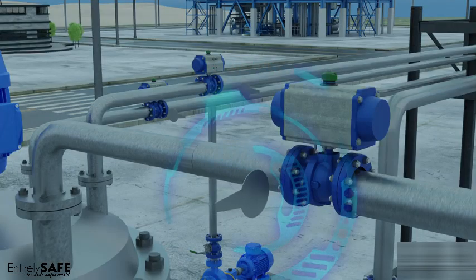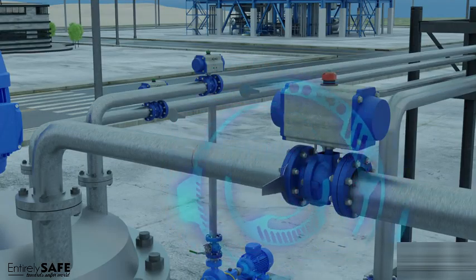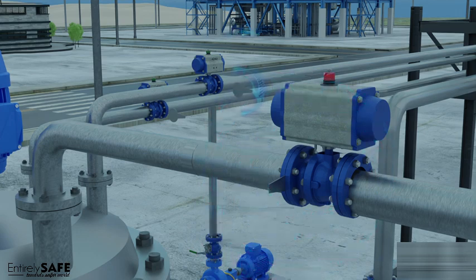The explosion could have been prevented by isolating the reactor by slip plates or physical disconnection. This incident and the others described show that using only valves as LOTO for isolation is not good enough. We must never underestimate checking the effectiveness of the isolation before releasing the permit to work.